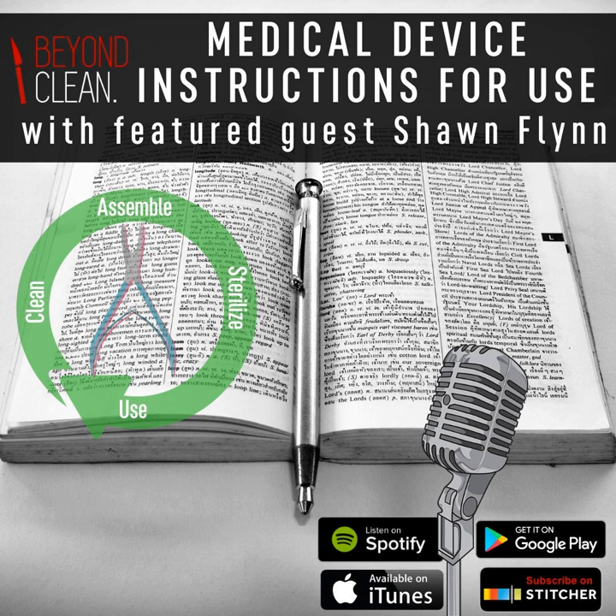That's a great point, Shawn. That complexity, if it exists, has to be overcome by writing it into the competency of the technician's training, with annual competency checkups to ensure that if there is variation in those cycles, everyone on the team, all three shifts and weekends, knows how to do this. It can't be something only done in the daytime, only when the lead tech is around. If they're not there, the device either sits on the shelf and waits, or it gets done improperly.